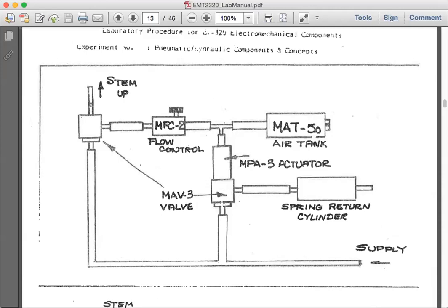As the pressure stops, there is no longer pressure coming into the right, and right away the stem is up. The pressure that was provided to the right now vents right away through the hole in the stem of the three-way valve, which is inside of the actuator, and there is a little hole in the actuator which allows it to further vent the pressure out of the system.